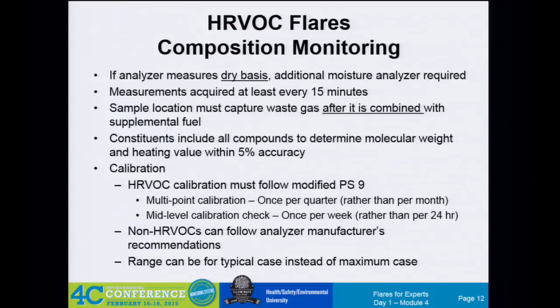The instruments have a 95% on-stream time required. If you're down for greater than 8 hours, then you're going to have to grab a sample. So there's a big push to keep your instruments up.